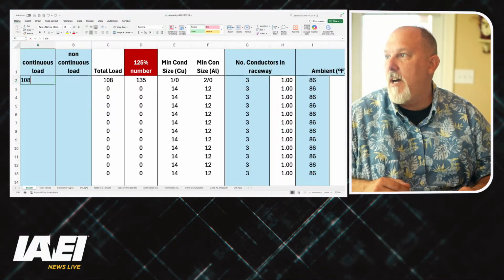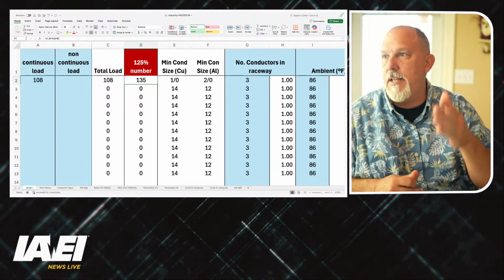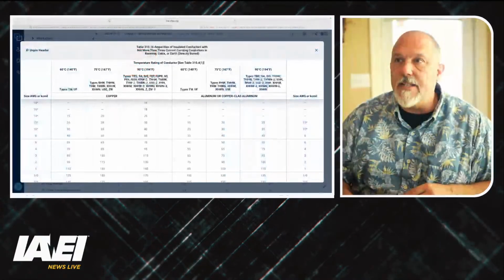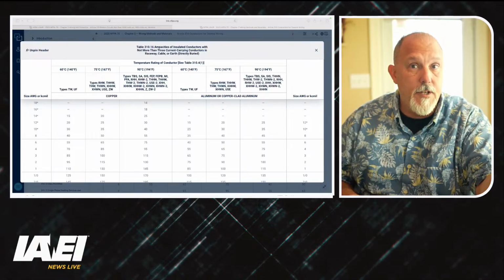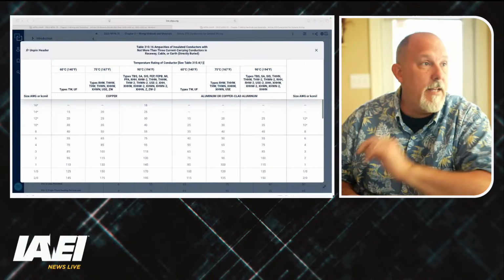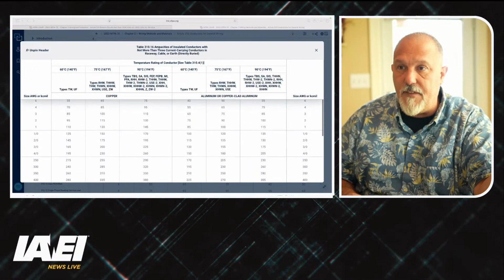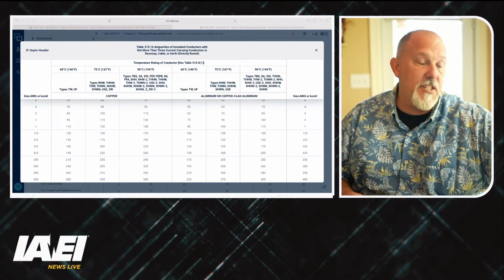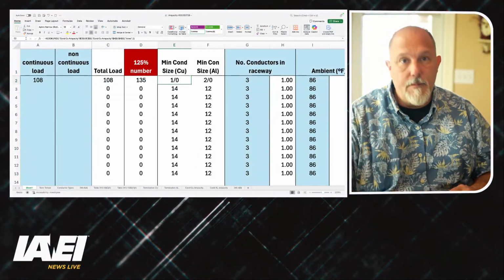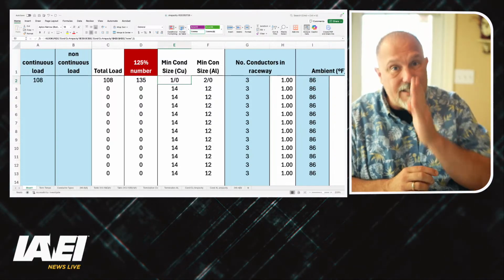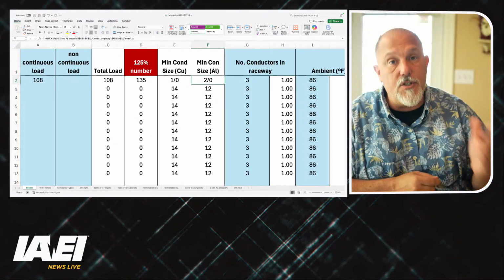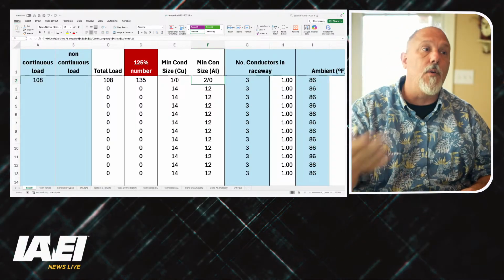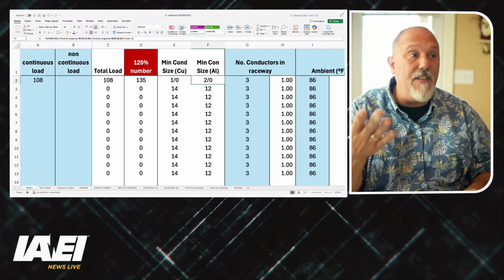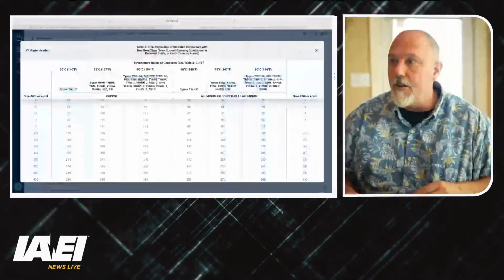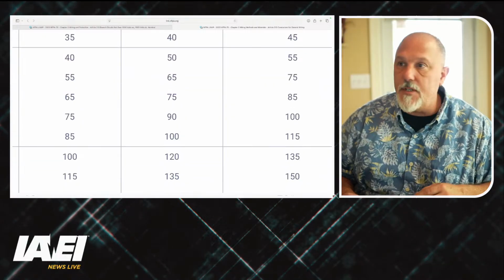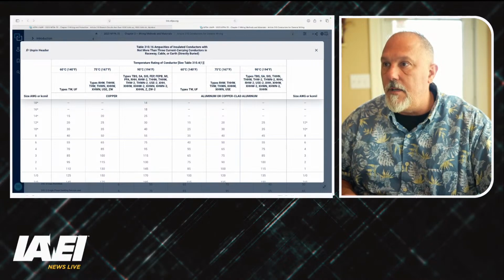So I have 108 amps of continuous current. That means 125% of the continuous current is 135 amps. What I do then is I come to, and this is going to be 75 degrees C equipment, so that's going to be my limiting factor. I come to the 75 degrees C column, and I have to find something that is equal to or greater than 135 amps, which means it's a 1-aught conductor. If I go back to my spreadsheet, for copper, my sheet's telling me my minimum size is 1-aught because it's using the 75 degrees C column. If I use aluminum, I've got to move that to a 2-aught. And that's because in the 75 degrees C column for aluminum, a 2-aught gets me to 135 amps exactly. So there's my 135 amps right here, 135 amps in the 75 degrees C column for aluminum.